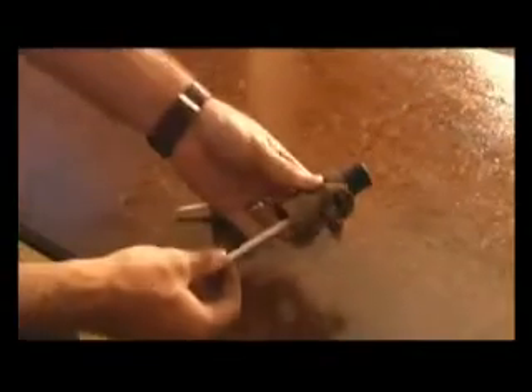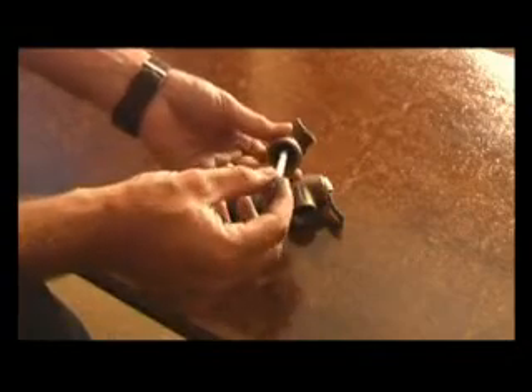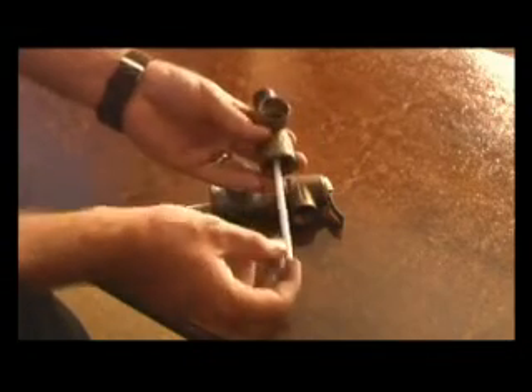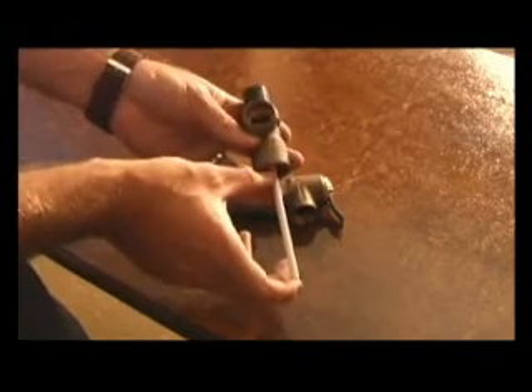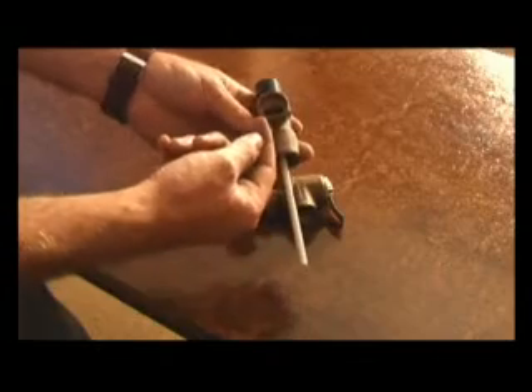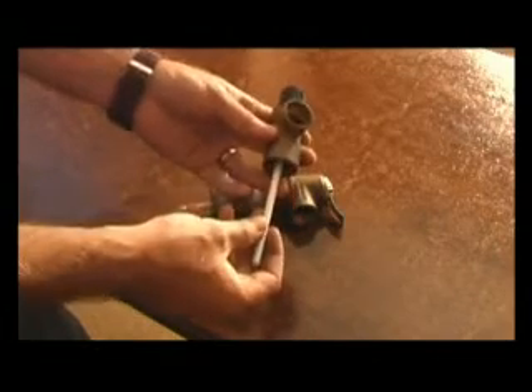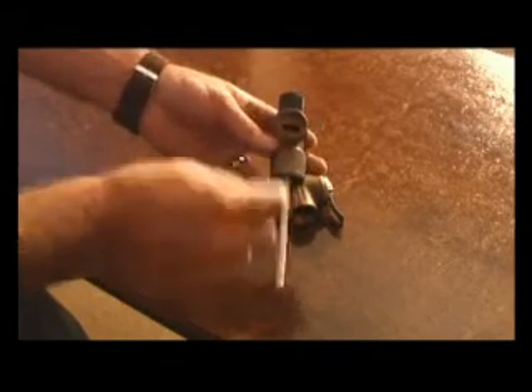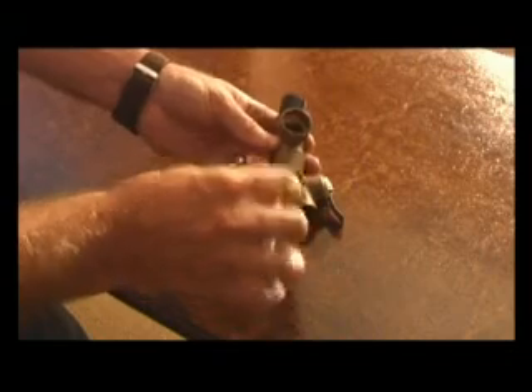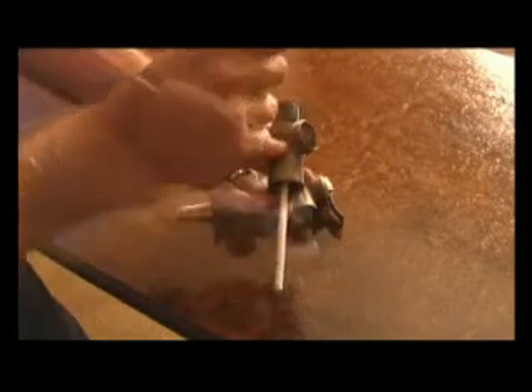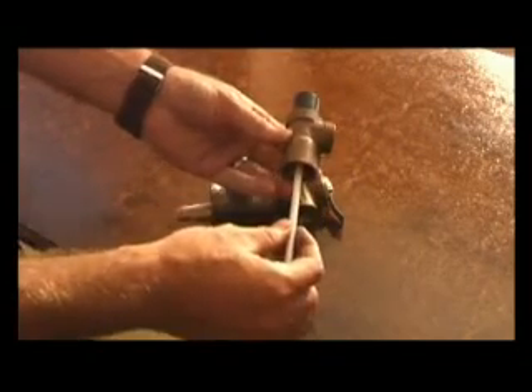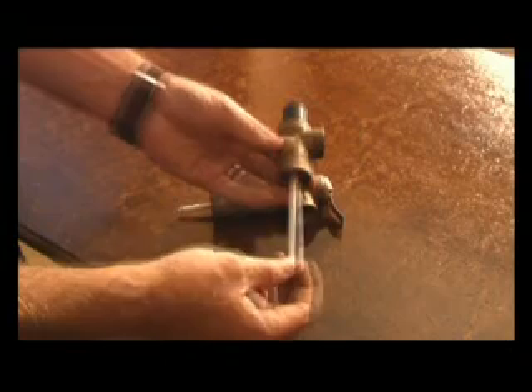A temperature and pressure valve has a probe which is inserted into the geyser, which has wax in it, and as the water heats up, the wax melts, and when the water reaches between 92 and 95 degrees Celsius, the little pin inside of the probe pushes open a jumper, releases the boiling water or the hot water, and lets in cold water from the mains.